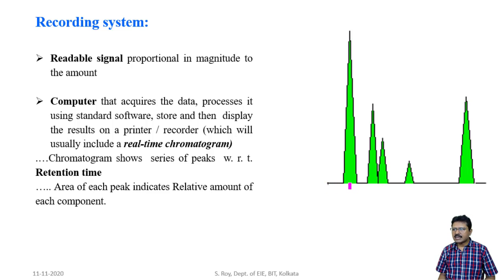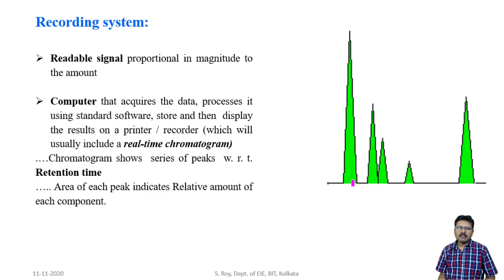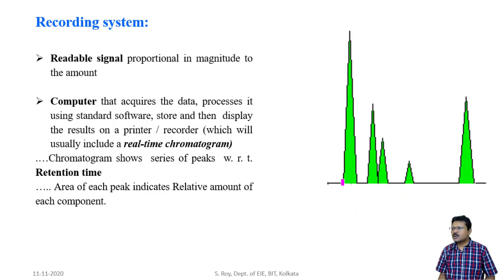According to the different retention times, we can identify which components are present in the mixture because the instrument is already calibrated. If the retention time is a certain value, the component will be identified as A; if another value, it will be B. The area of each peak indicates the relative amount of each component: a higher area means a higher concentration, and a lower area means a lower concentration.